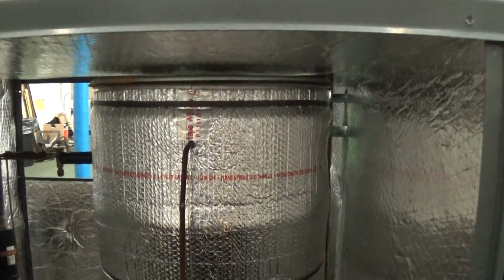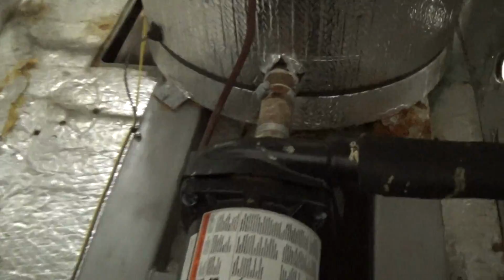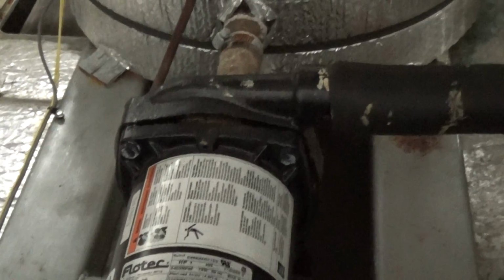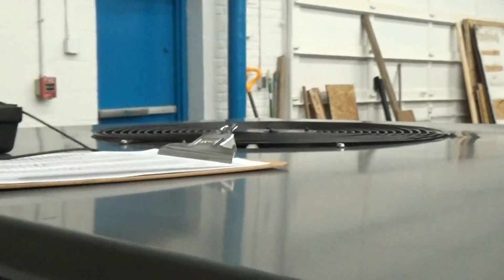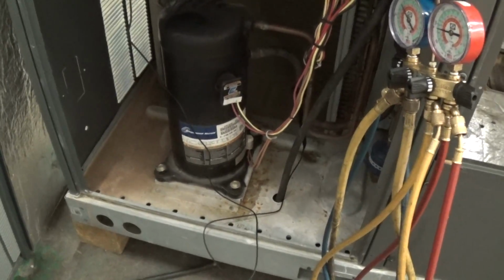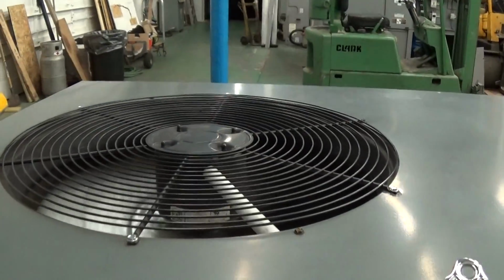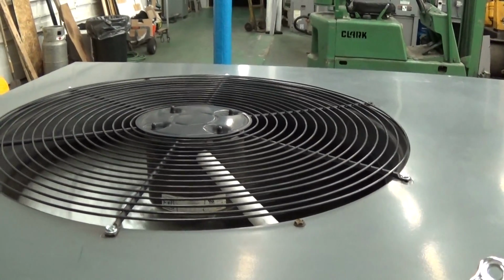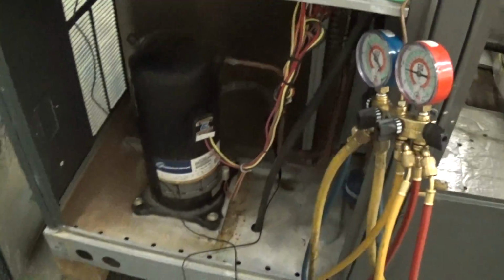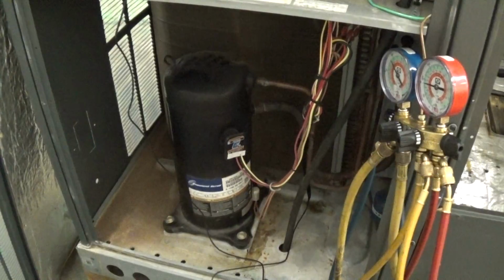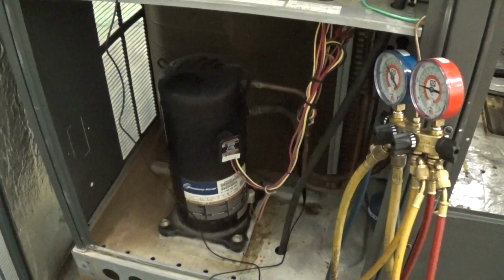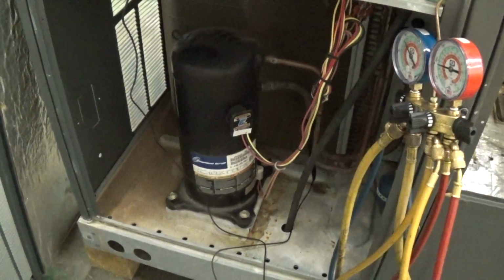We got about a 55-gallon stainless insulated reservoir here. Before it ships out, we're going to insulate the head or the impeller in this section coming off the tank. This is a 1-horsepower single-phase process pump, Flotec process pump. And the fans are also single-phase. So very important for this unit when you start up, you cannot assume you have the right fan rotation because the fan's blowing the air upwards as it should. It's going to do that no matter what. So it's important to call us upon startup or have an HVAC technician there to check the pressures so they know that the Copeland scroll compressor is rotating in the right direction.